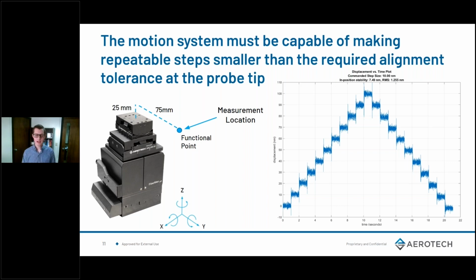We took that bottom axis, commanded 10 nanometer steps, and you see the cap probe output on the right-hand side in the plot. You'll see in that plot that first off, there is some noise. That noise is about plus or minus 3 nanometers or so, peak to peak. So you can see that the noise in the plot is smaller than the step size we're making, so the steps are very resolvable. You can see that the steps are very consistent forward and backward.